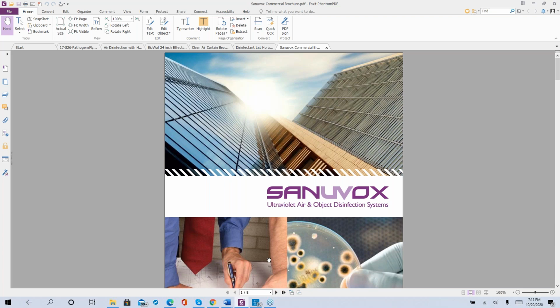But that BAS screen can also help you interlock, but a lot of businesses and buildings just don't have BAS systems, building automation systems, energy management. So instead, if you're going to be mounting this separate and away from the unit, then that airflow switch is going to sense the airflow and light the UV light only on airflow. So you don't need to spend the money on irradiating duct with no airflow, even though they only draw around 6 amps, and these can be wired to 110 or 277 or 480 for your voltage.